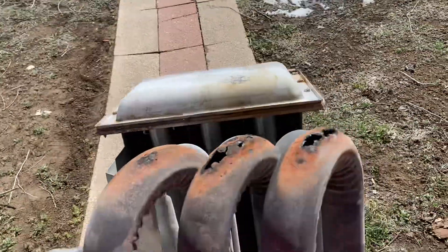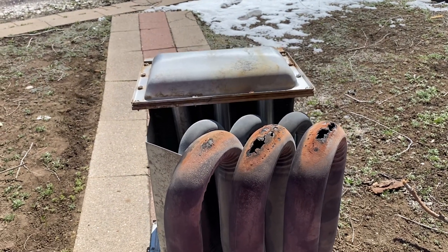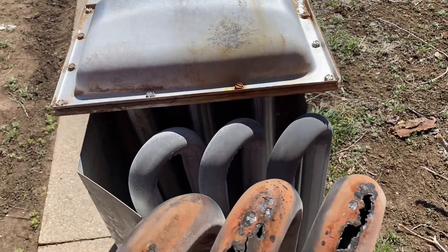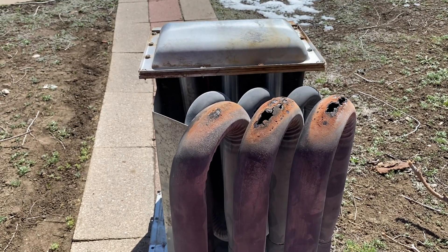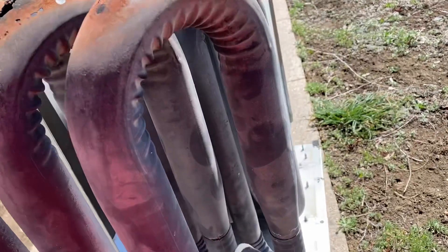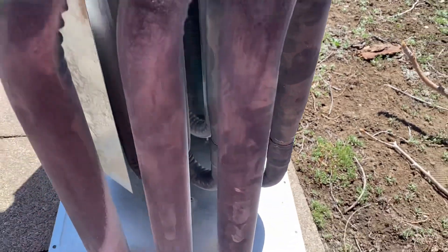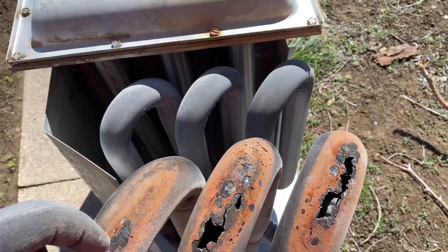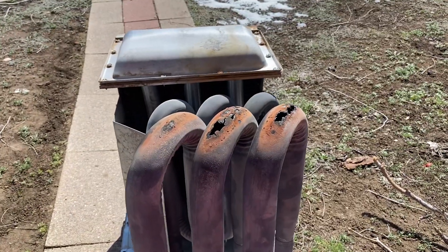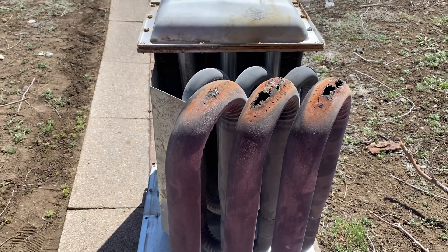That's what makes me believe there was a problem with this from day one. I think this was cracked, and instead of somebody fully investigating it and seeing what was wrong, they should have been able to see a crack in these when they were unpackaging the unit. I always check what I'm putting in on a new furnace because they're mass produced. There were also hairline cracks down here as well. Why else would they have turned down the gas pressure?